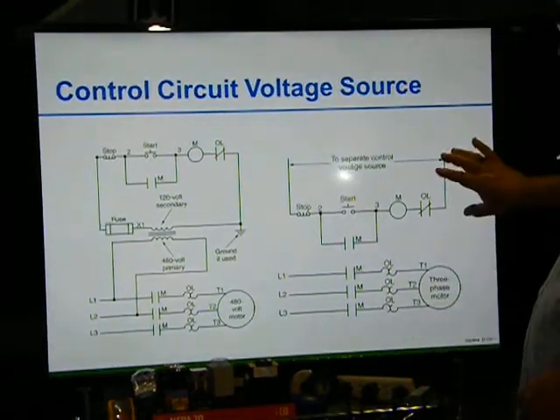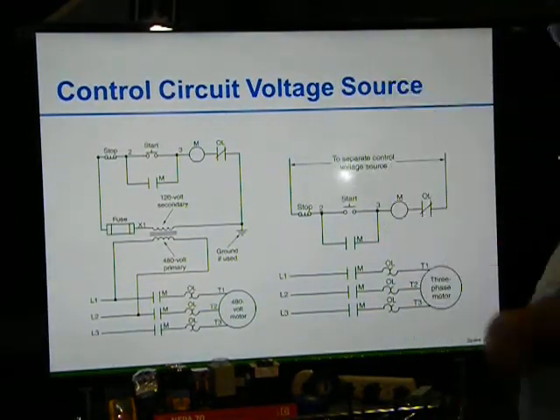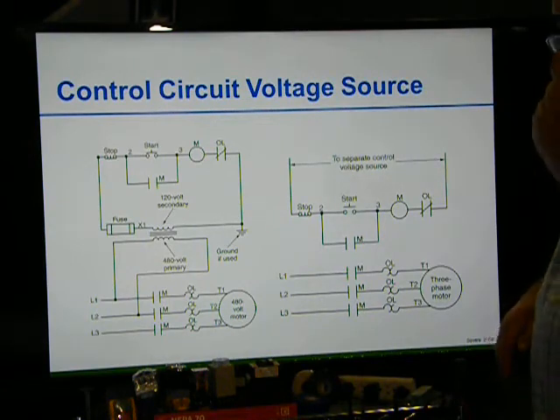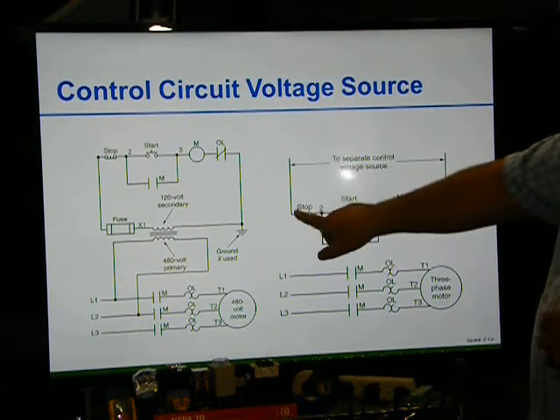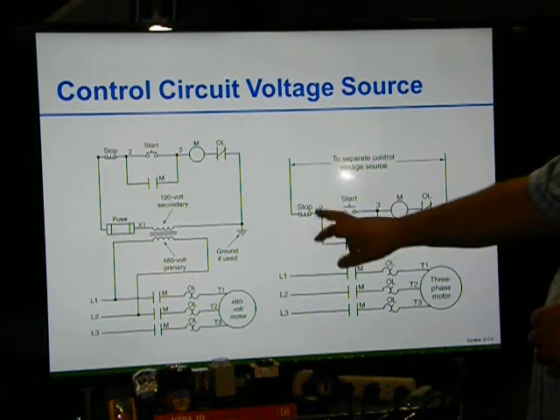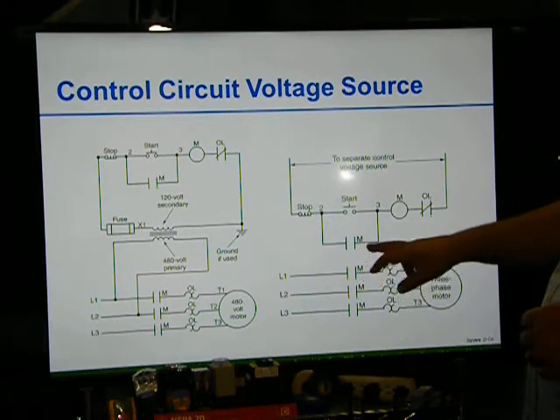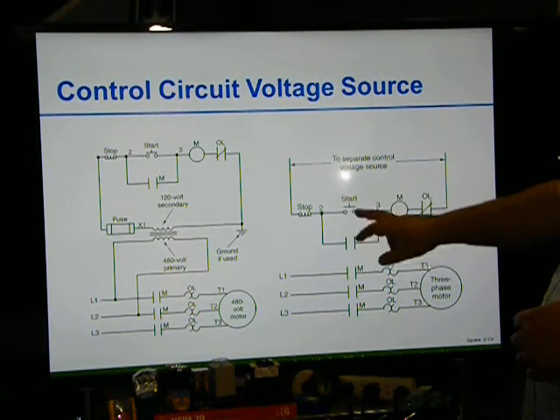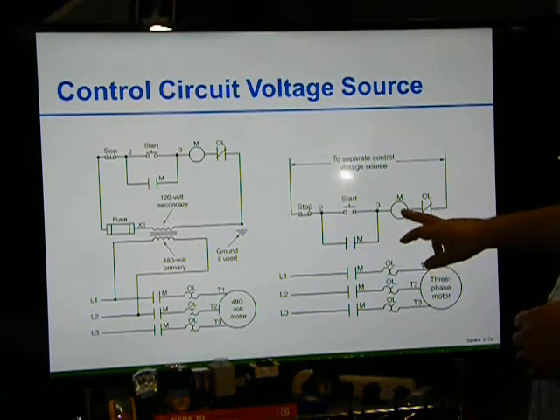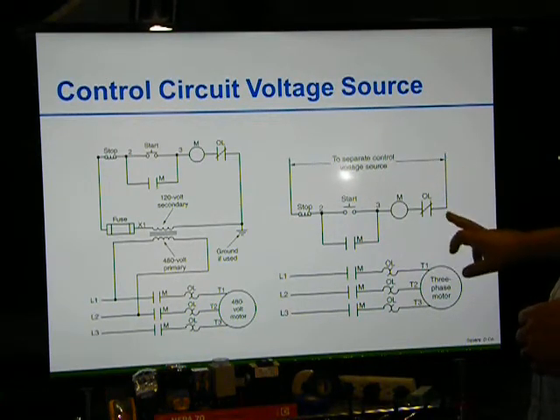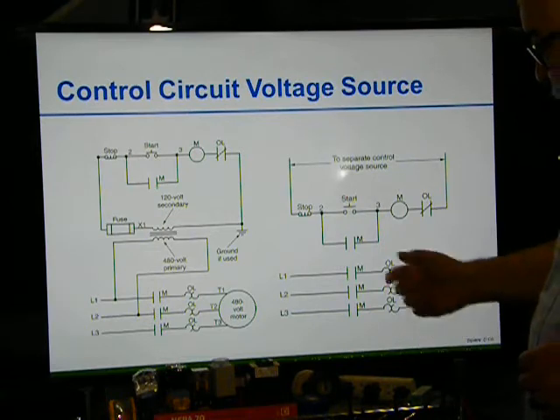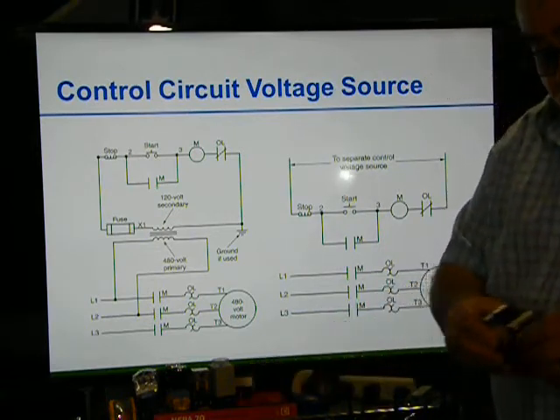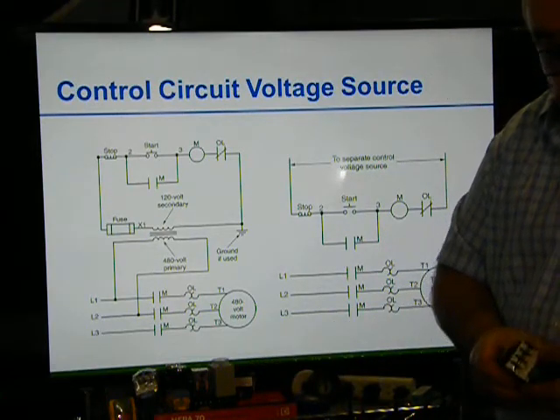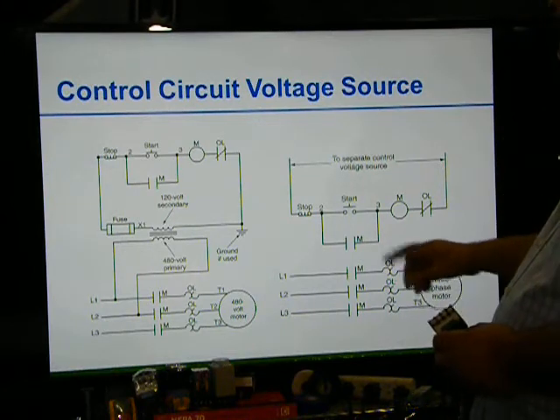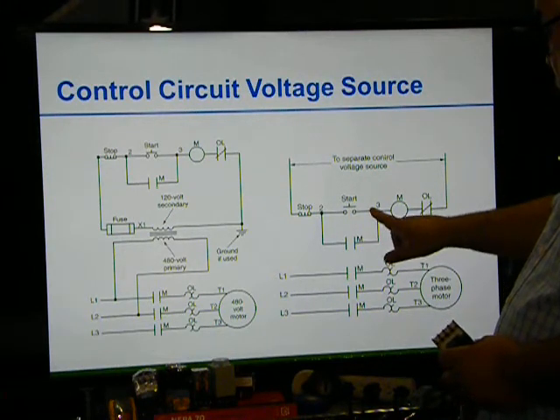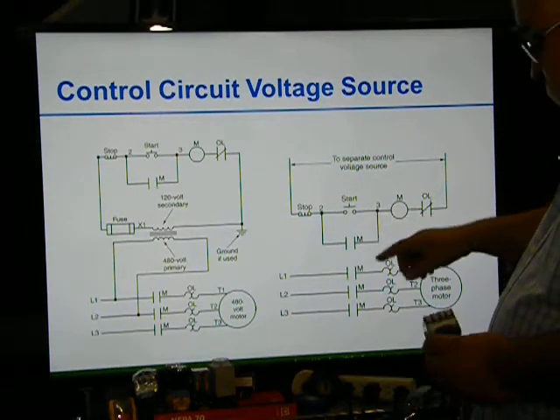And then we can also bring a separate source. Bring a circuit from somewhere else, 120 volts, and bring it in. So we bring on a circuit. Here's the stop starts. It goes into our auxiliary contacts, then goes to our motor or coil. Say this is our neutral coming in, and on this contactor here, it would go to the A1.